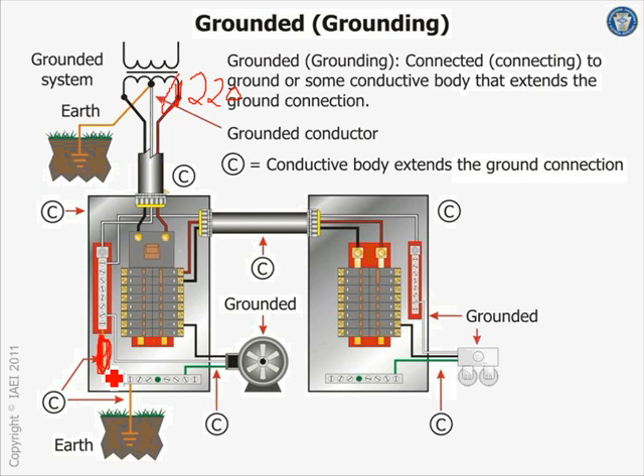So then what people do is they have concrete encased electrodes. Most of the buildings are done with concrete. So rebar around the whole building. This is the best. Concrete encased electrodes are the best electrodes. And you put it up here, and then you tie it to the water pipe system, which is becoming less and less reliable all over the world with the PVC that they use. And between the grounding electrode conductor, they'll give you very low impedance, 5 ohm, and that's an acceptable way of returning your ground fault all the way to the source.